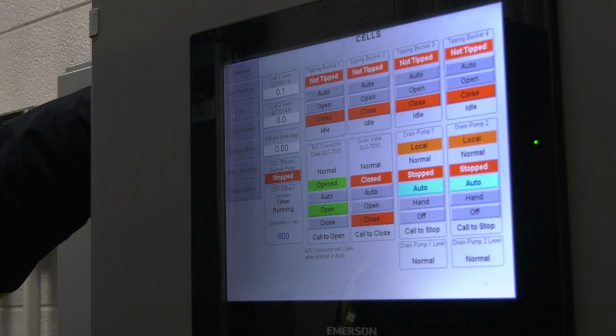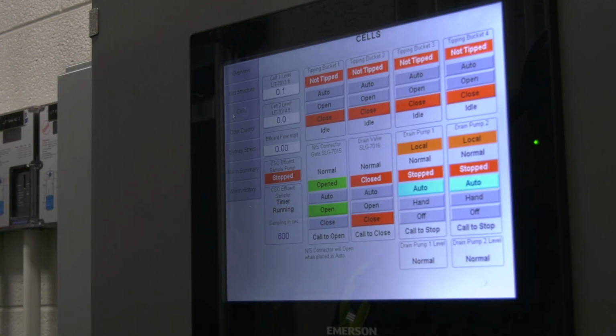All right, stormwater screen. When the stormwater level at LIT 7012 rises above 5.3 feet, the screen will be called to run until the high level falls below 5.3 feet. The screen will be called to run if its auto signal is on and the oil temperature high is off and the low level oil is off and the motor overload is off. And I believe there's a control panel downstairs for the screens, correct? It's right out here. Okay.